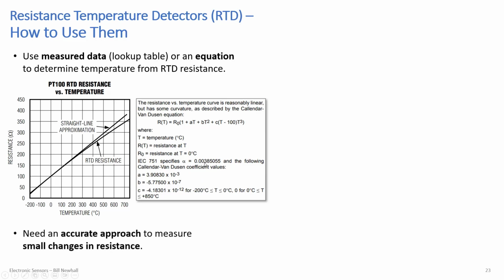So now that we have this resistance that starts out at 100 ohms at 0 degrees C and goes up to 350 ohms at around 600, we need some way to accurately measure very small changes in resistance, because if you're just changing a few degrees, you're not getting that much of a resistance change. You'll see this is a common problem, especially when we get to strain gauges.